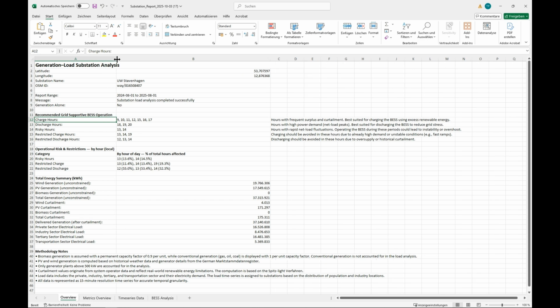What's very important for discussions on grid-supportive BESS operation is, if you're planning a battery storage there, how would you operate it? To be grid supportive, based on the generation profile of the wind and PV plants nearby, but also the load consumption in the area, we recommend charging hours like 9, 10, 11, 12, 15, 16, 17 o'clock, and discharge hours in the evenings, around 18, 19, 20.